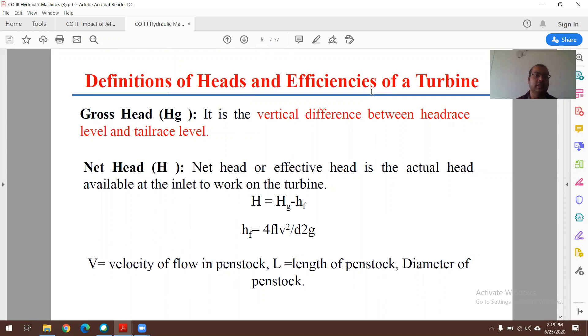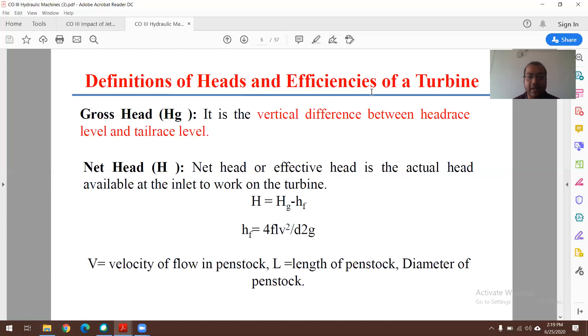Gross head is the vertical difference between the headrace and tailrace levels. Net head equals gross head minus head losses. The frictional head loss hf is given by the formula: hf = 4fLV²/2gD, where V is the velocity of flow in the penstock pipe, L is the length of the penstock, and D is the diameter of the penstock pipe. Net head is obtained from this expression.